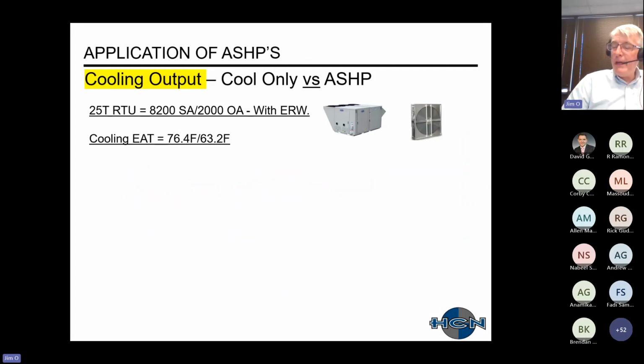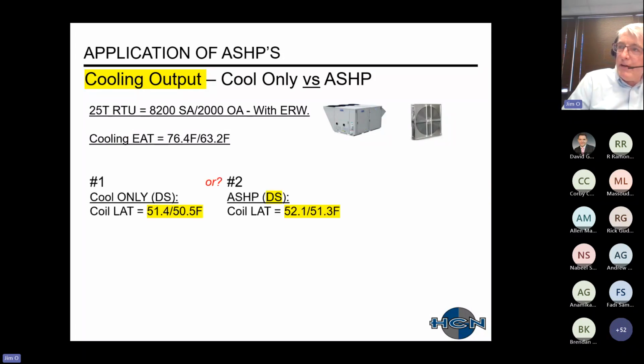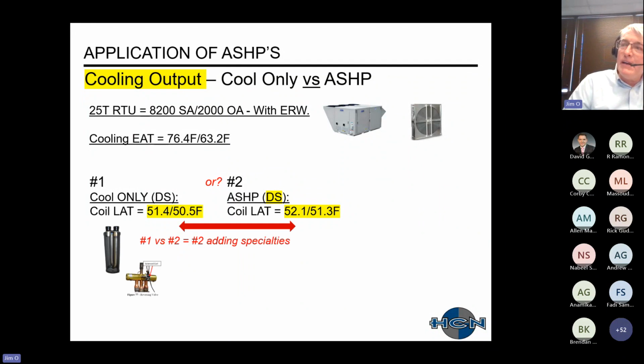So first, I just want to compare a cooling-only unit versus an air source heat pump. There are the conditions in my entering air temperature there. If you compare a cooling-only unit versus an air source heat pump, what will end up happening is that your leaving air temperature in cooling will probably slightly increase. I attribute this to what I would expect, that you're adding specialties to the refrigeration system, such as the suction accumulator and that four-way valve. So you'll have a little bit more inefficiency introduced to your refrigeration system.